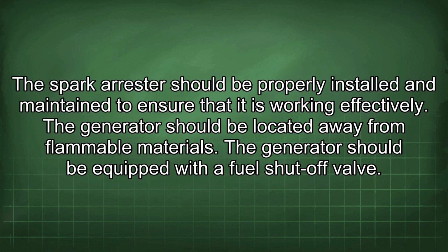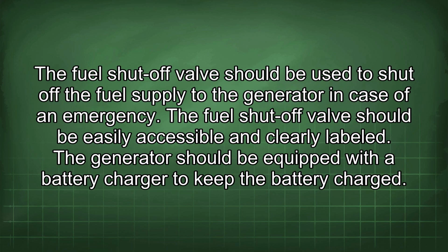The spark arrestor should be properly installed and maintained to ensure that it is working effectively. The generator should be located away from flammable materials. The generator should be equipped with a fuel shut-off valve. The fuel shut-off valve should be used to shut off the fuel supply to the generator in case of an emergency. The fuel shut-off valve should be easily accessible and clearly labeled.